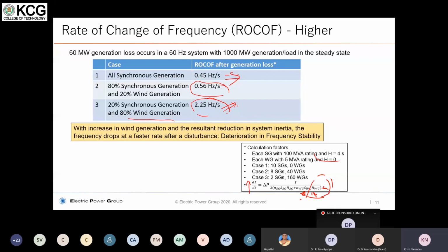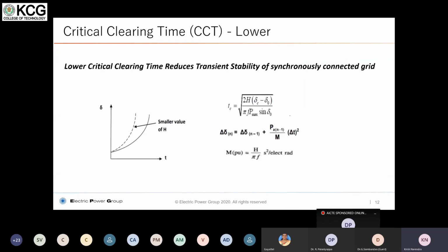That is dangerous. And thirdly, let us see how the critical clearing time is directly proportional to H. When H decreases, your Tc, the critical clearing time, also decreases, and you can see the curve getting into the unstable region already in your system. And therefore, the lower critical clearing time reduces the transient stability of the synchronously connected grid.